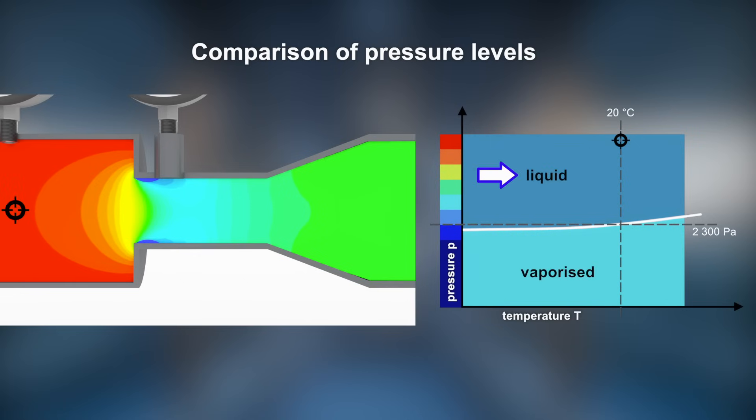Upstream of a restriction, the static pressure is well above a vapor pressure. The static pressure in the flow decreases as the flow reaches the narrow pipe section. In our example, the pressure at the exposed edge is below the vapor pressure. Consequently, water evaporates and cavitation bubbles are formed.